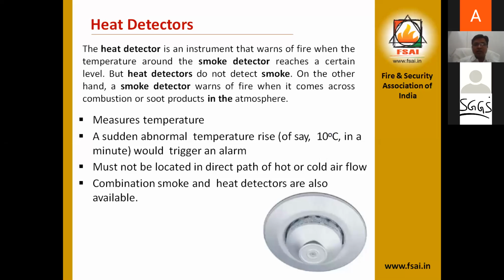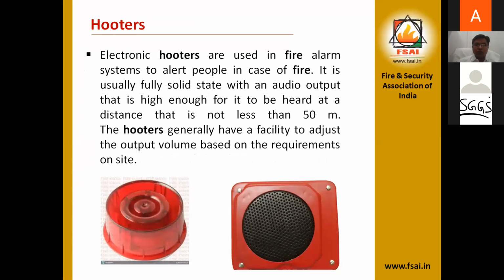Next is the hooter. It is an electronic hooter used in a fire alarm system to alert the people in case of fire. It is usually fully solid state with an audio output that is high enough for it to be heard at a distance of not less than 50 meters. So we can hear the sound at a distance of 50 meters when it starts buzzing. The hooters generally have a facility to adjust the output volume based on the requirements on the site.